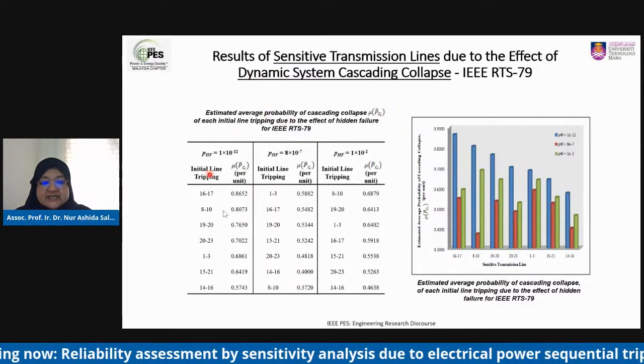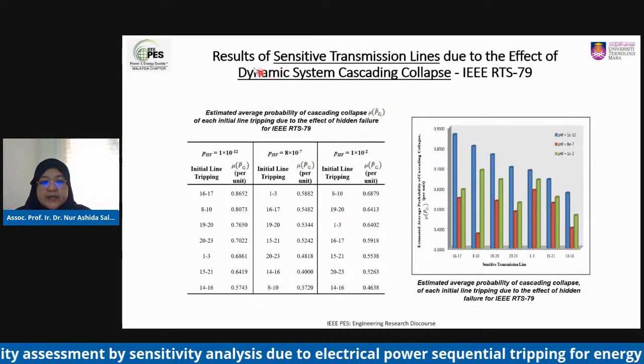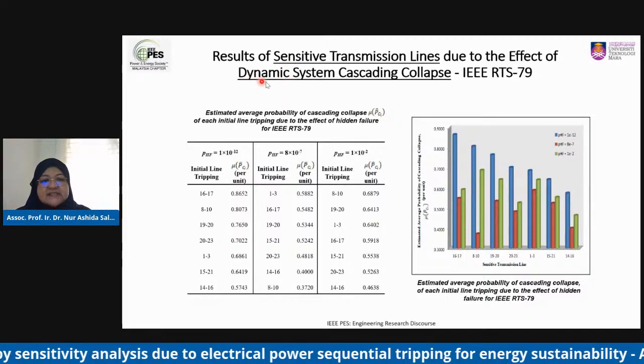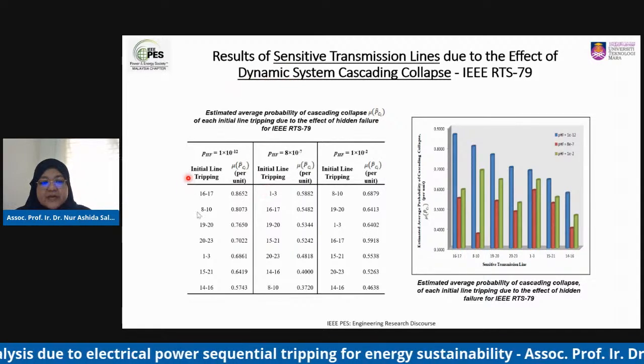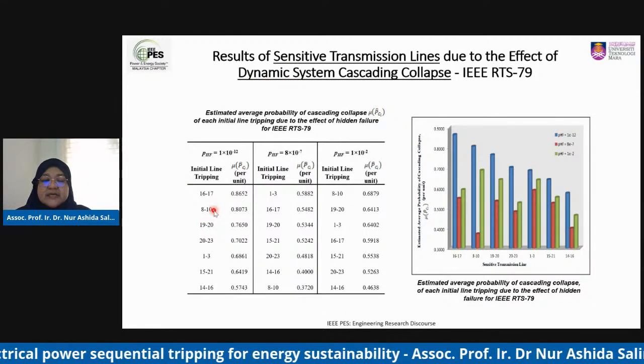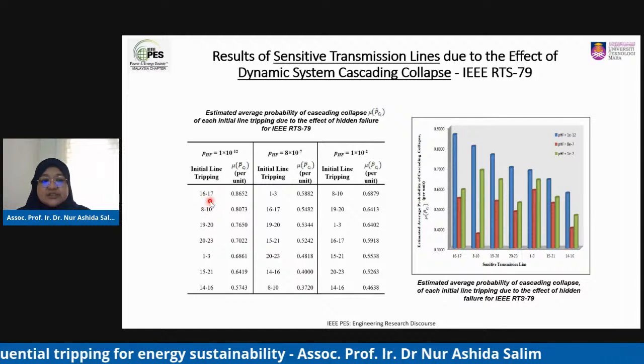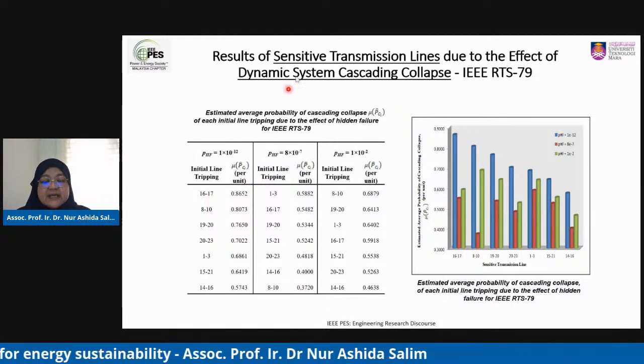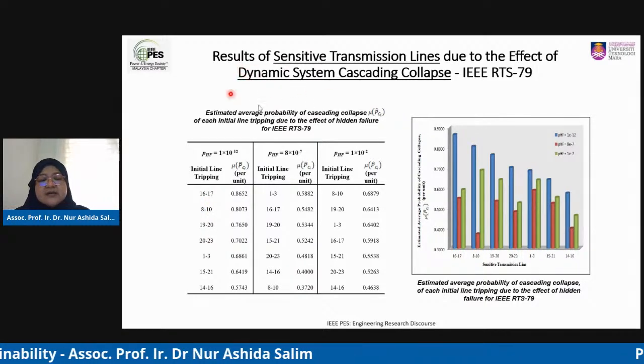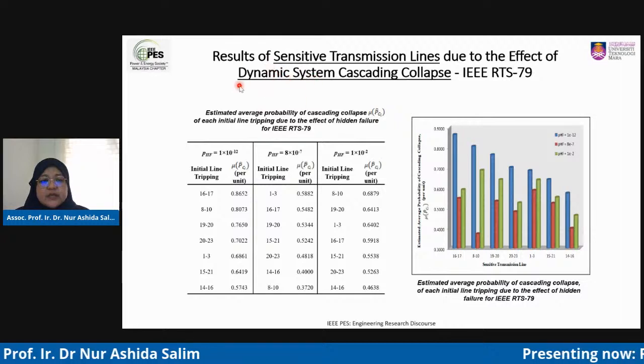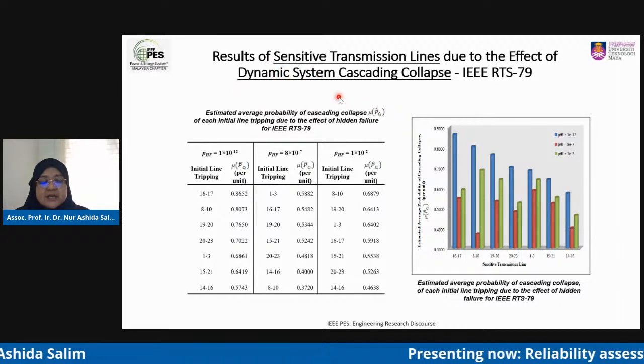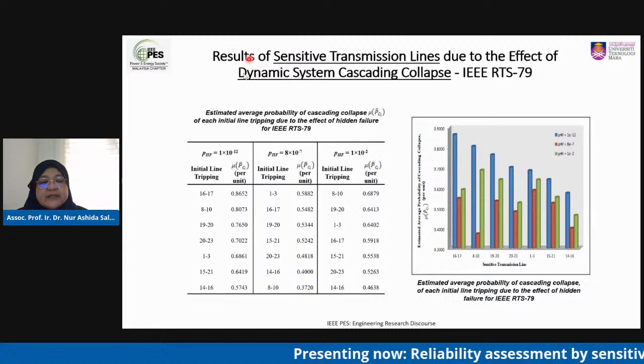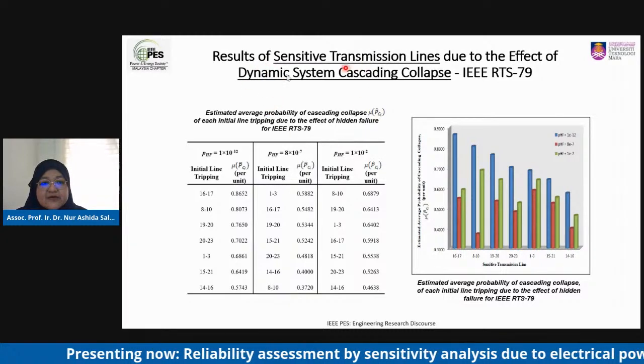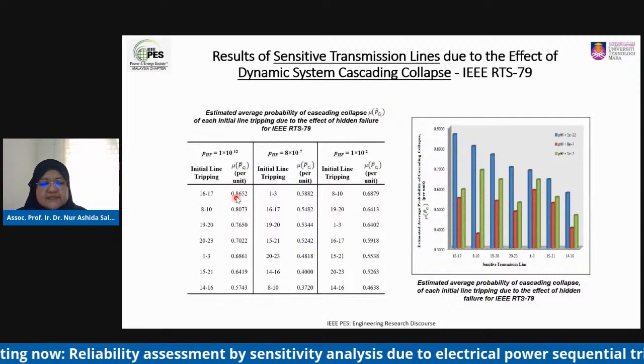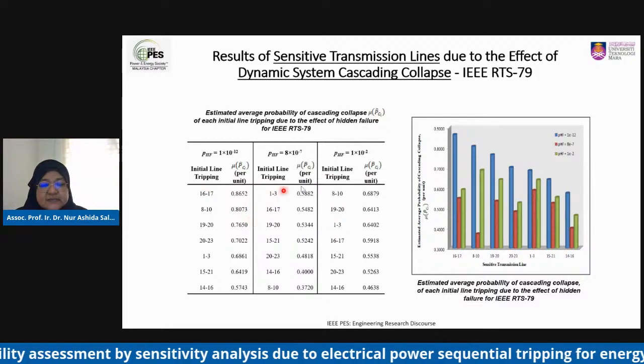So basically, these results are tabulated when we perform the dynamic system cascading collapse, testing by initial tripping for each transmission line. We then calculate the critical clearing time for that particular generator.